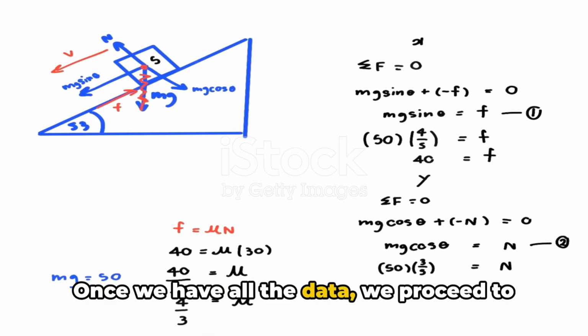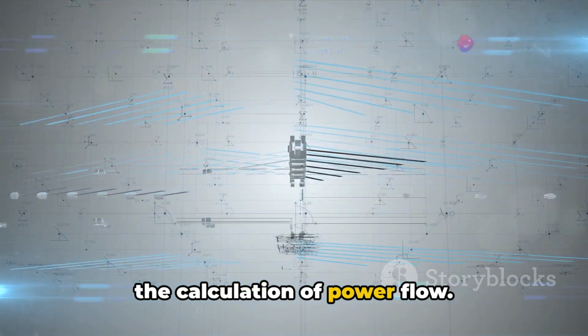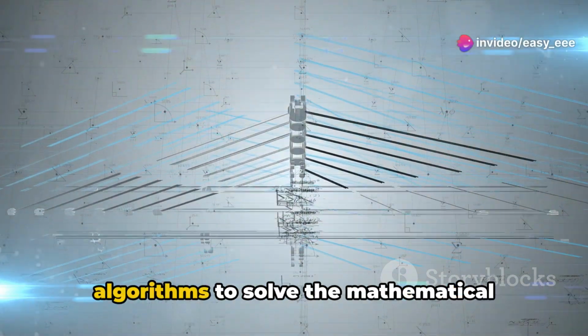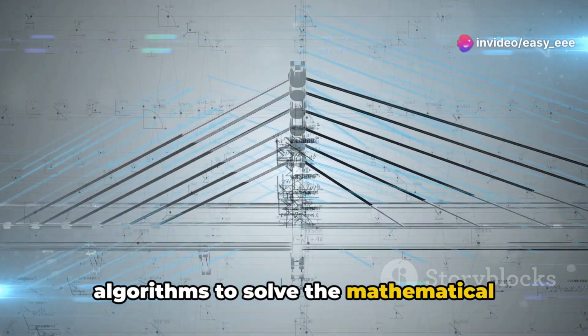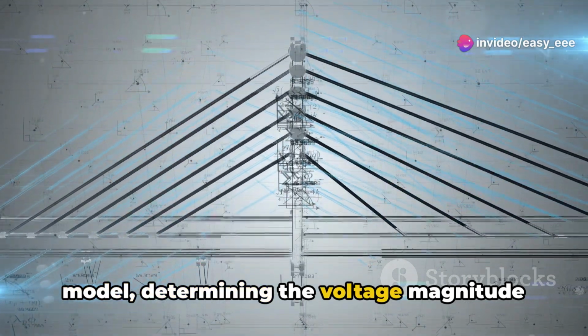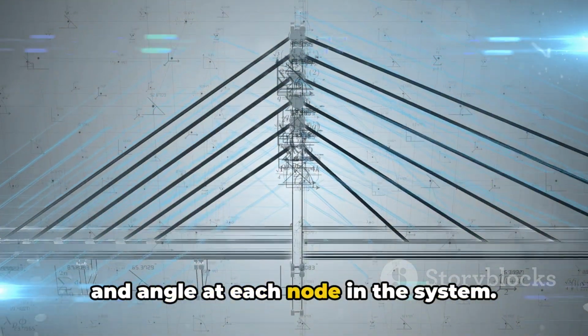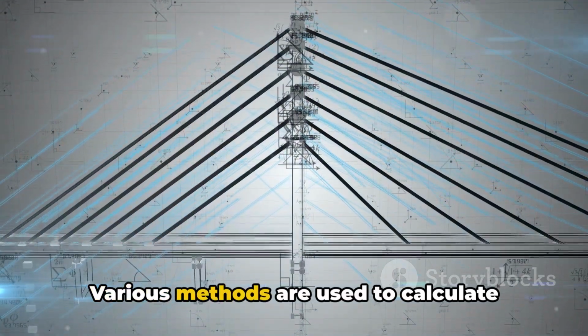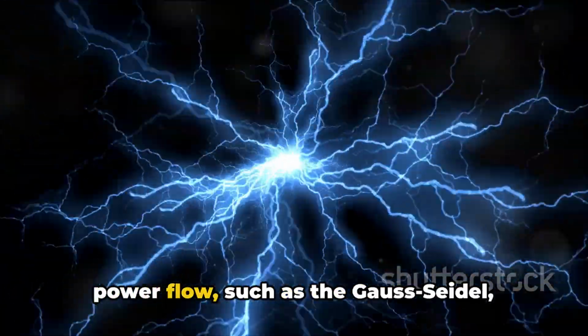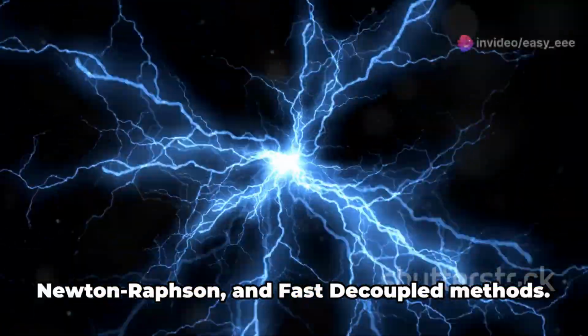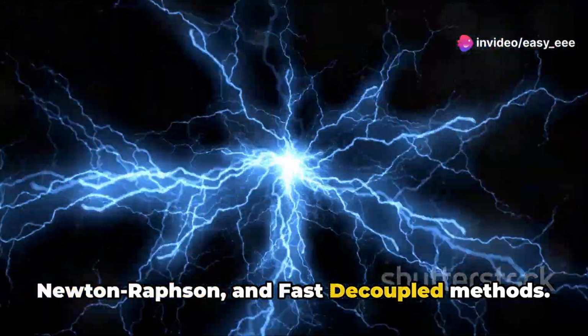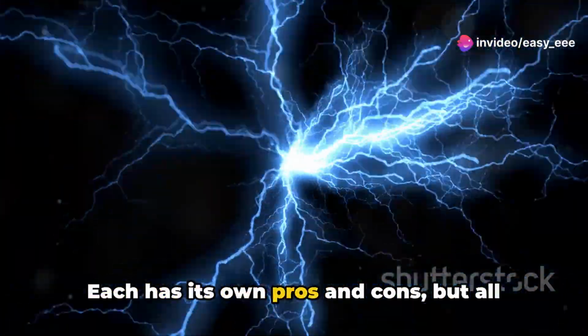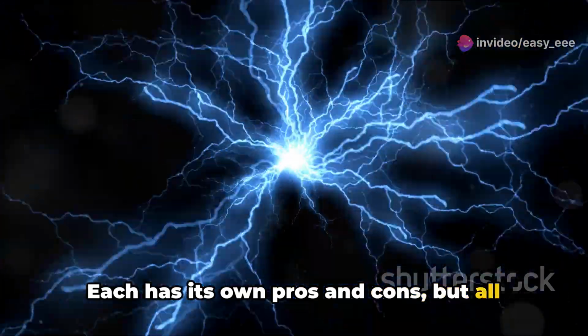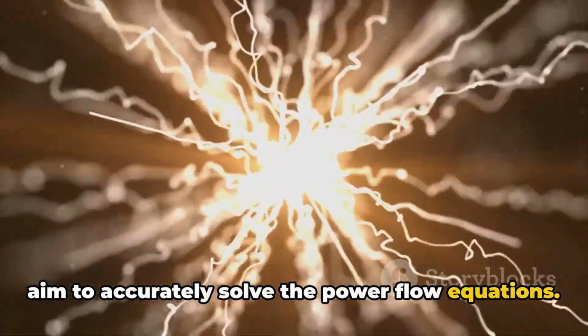Once we have all the data, we proceed to the calculation of power flow. This is where we apply a set of algorithms to solve the mathematical model, determining the voltage magnitude and angle at each node in the system. Various methods are used to calculate power flow, such as the Gauss-Seidel, Newton-Raphson, and fast decoupled methods. Each has its own pros and cons, but all aim to accurately solve the power flow equations.